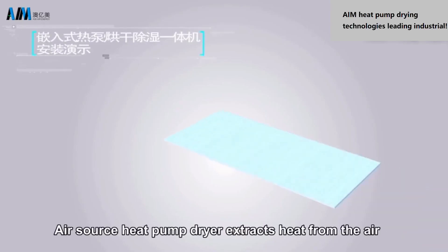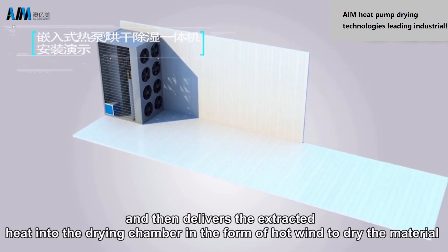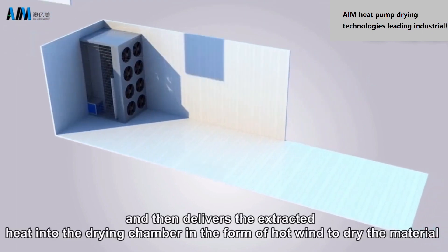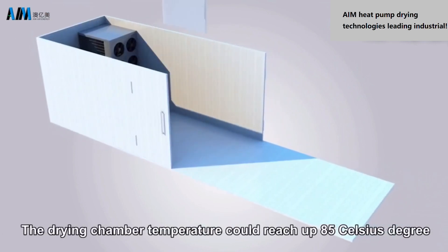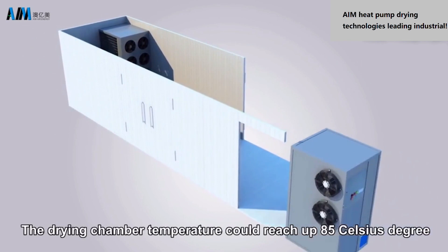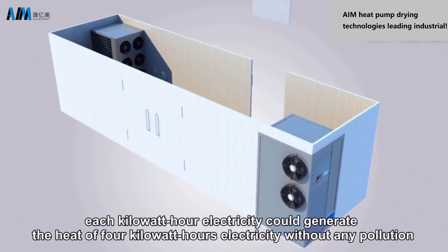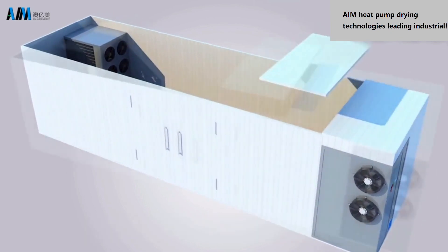The heat pump dryer extracts heat from the air and then delivers the extracted heat into the drying chamber in the form of hot wind to dry materials. The drying chamber temperature can reach up to 85 degrees Celsius. Each kilowatt-hour of electricity can generate the heat equivalent of 4 kilowatt-hours without any pollution.